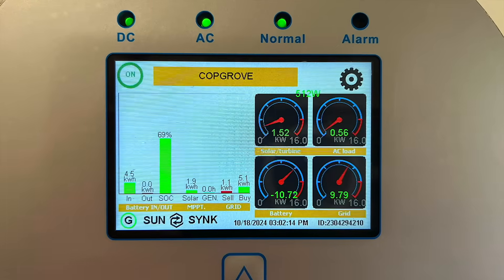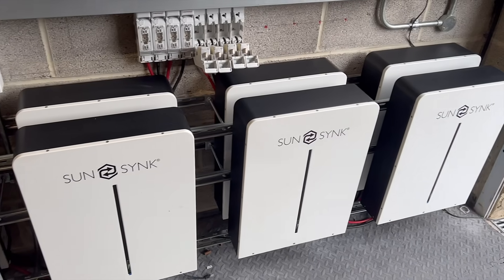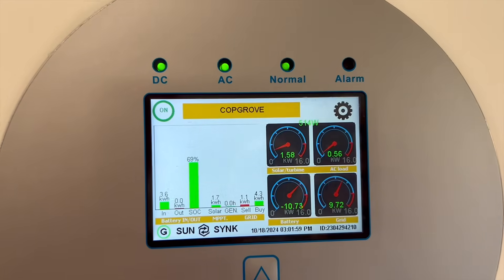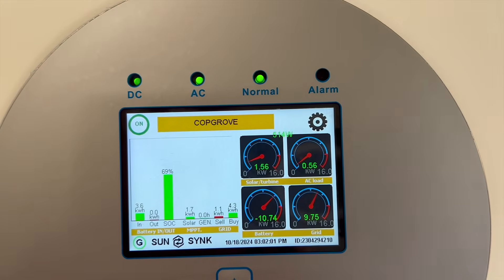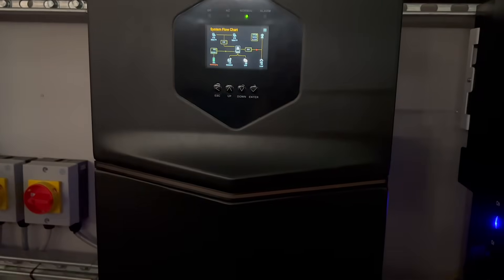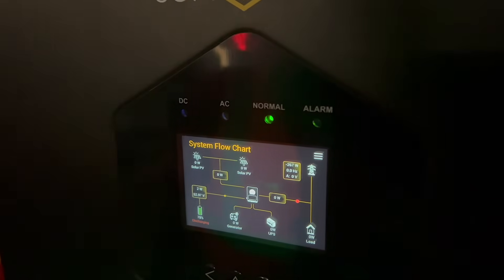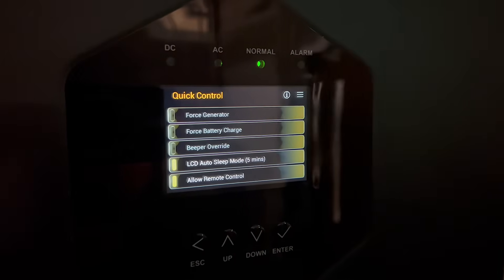Fortunately, that's where temperature control systems step in — what we call the BMS, or battery management system. The BMS is effectively the brain of the battery storage system. It doesn't physically control the charge or discharge current, but it does track what's happening inside every single cell: things like temperature, voltage, and state of charge, to keep the system operating safely. When it turns cold, the BMS communicates with the inverter, telling it to slow down, adjust, or even pause charging and discharging to protect the cells. In other words, it's the built-in safety net that keeps the battery healthy, efficient, and protected, no matter what the temperature outside is doing.